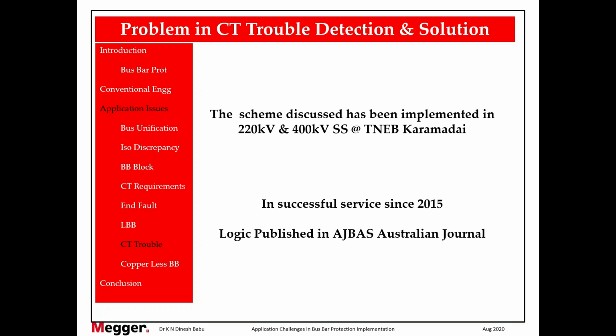there is no need for using any additional equipment. With the use of advanced logic, we can simply modify the existing relay itself and get this information done. I repeat, there's no need for using additional equipment to identify the CT trouble issue. With the use of advanced logics, we can simply modify the existing relay itself. So all we need to do is to just update the specification and get this implemented. Thank you.